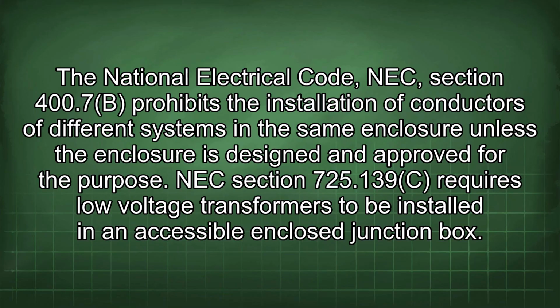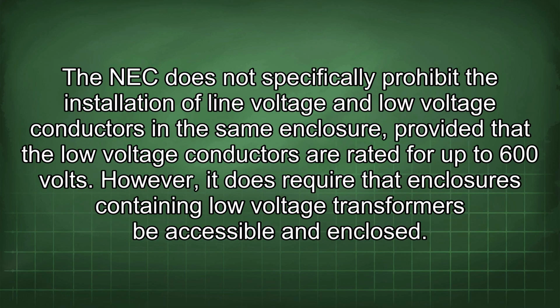The National Electrical Code, NEC Section 400.7b, prohibits the installation of conductors of different systems in the same enclosure unless the enclosure is designed and approved for the purpose. NEC Section 725.139c requires low-voltage transformers to be installed in an accessible enclosed junction box. The NEC does not specifically prohibit the installation of line-voltage and low-voltage conductors in the same enclosure, provided that the low-voltage conductors are rated for up to 600 volts. However, it does require that enclosures containing low-voltage transformers be accessible and enclosed.